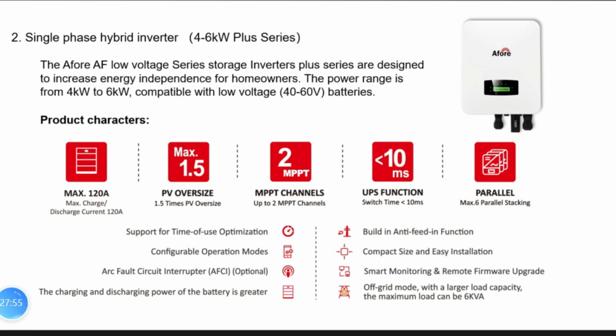So all versions of the inverter are equipped with a built-in anti-islanding function, and we provide a Wi-Fi dongle as standard, so the users or operation and maintenance staff can do firmware upgrades remotely, and also some of the operational modes and parameter settings can be done online. And for some countries or regions, they need the arc fault circuit interrupter, so we provide this as an option to meet the local authority requirement.